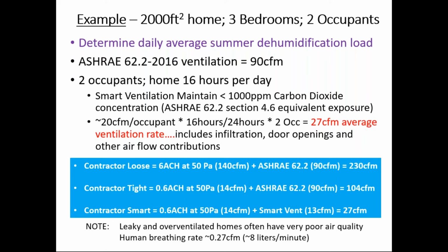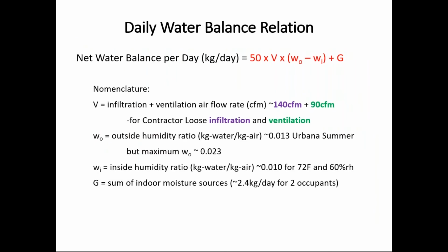I'd also make the comment that even though 27 CFM sounds low, if you ever put a spacesuit on or diving scuba gear, the rate at which fresh air needs to be delivered to you for breathing is just a hundredth of 27 CFM. 27 CFM is basically what's needed to keep that environment around you so that this mixed air is roughly polluted. But if you were to wear a spacesuit or a stillsuit or something like that, much, much less fresh air is needed to be directly delivered to your nose.